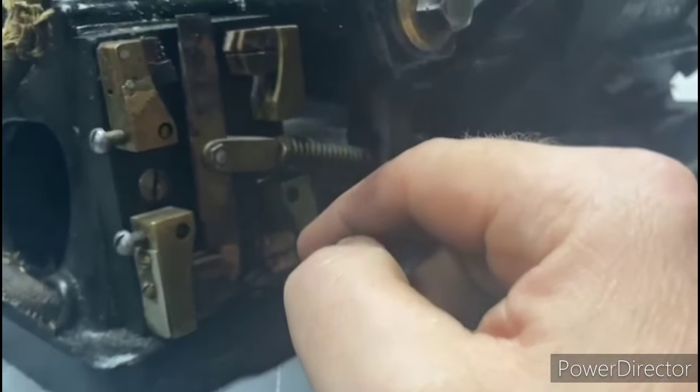We are going to have to do some machining of a couple new parts. Over here, this bolt has its head snapped off, so we're going to have to get that out because we won't be able to take these wires out until that bolt is removed — and that's going to be a delicate operation. There's also a screw that's missing over here on this sight glass. I haven't taken it apart yet to look at what's going on internally with the bearing assembly, but once we get in there we'll have a better idea.